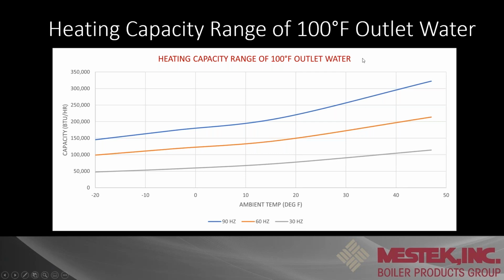At 100 degree water, just to keep this simple, we'll look at the 30 hertz at minus 20 degrees. We're going to get about 50,000 BTUs. If we ramp up to high speed, 90 hertz, we're going to be somewhere around 150,000 BTUs at minus 20 degrees. If we follow this up, and let's say it's 40 degrees outside, we're getting close to 300,000 BTUs at 100 degree outlet water temp at 90 hertz. I think you get the point on the other lines. Just keep in mind, that's 100 degree water.